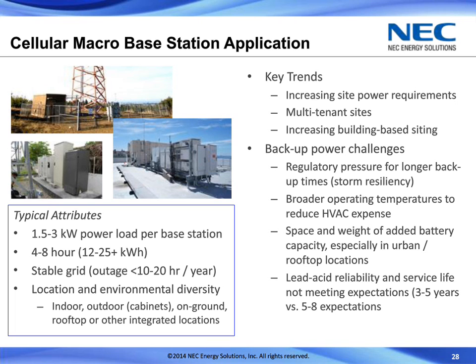So some typical attributes of these applications: 1.5 to 3 kilowatts of power, around 4 to 8 hours runtime. And one important thing is a stable grid for these applications, fewer than 10 to 20 hours of runtime a year. So as Bob mentioned earlier, the two components to the service life would be the float life and the cycle life. So for this particular application, you're more concerned with the float life due to the low cycle count. Also, environmental diversity with these, so you want to be able to withstand wider temperature ranges.